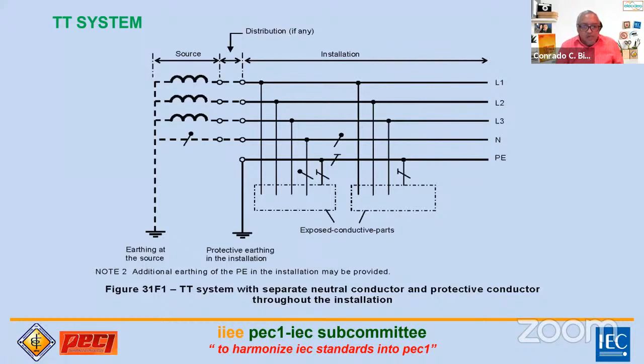So makikita mo, if you see this diagram, yung earthing ng source, it's here. Yung earthing ng installation, yung mga exposed conductive parts, is through yung grounding earthing rod na tinatawag. Meron dito. So hindi siya directly connected. Kita natin dito. So paano yan? Here in our code, yung earth, between the two rod, is not effective. Yung path of any ground fault, hindi siya effective kasi merong resistance. So magkakaroon tayo ng issue. So it's not allowed here to use yung TT na ito.